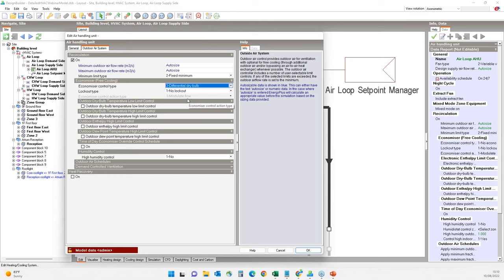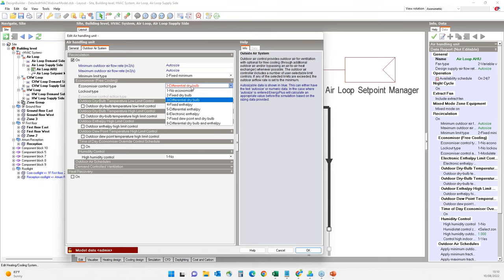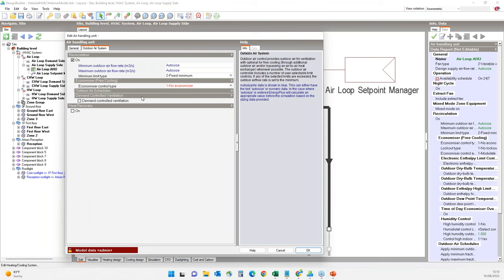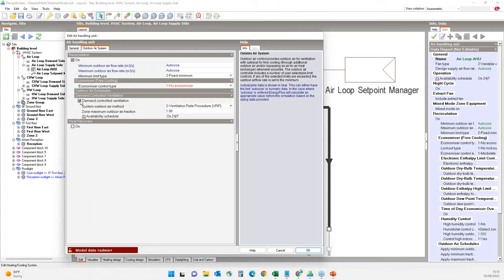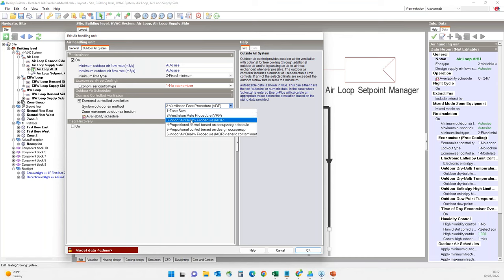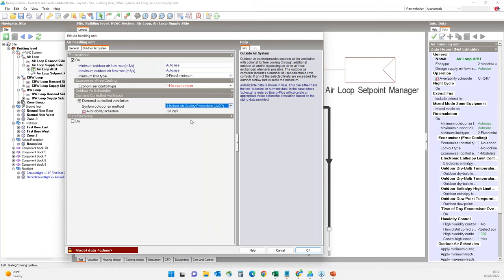Program help covers these components in detail and all the settings. You can access program help by clicking the help button on the dialog or using the help menu item on the toolbar. For now we will not include an economizer in our model, but we can include demand control ventilation. Using the outdoor air method based on indoor air quality procedure, defined as per ASHRAE Standard 62, it will calculate the amount of outdoor air necessary to maintain specific indoor CO2 levels in the zones.